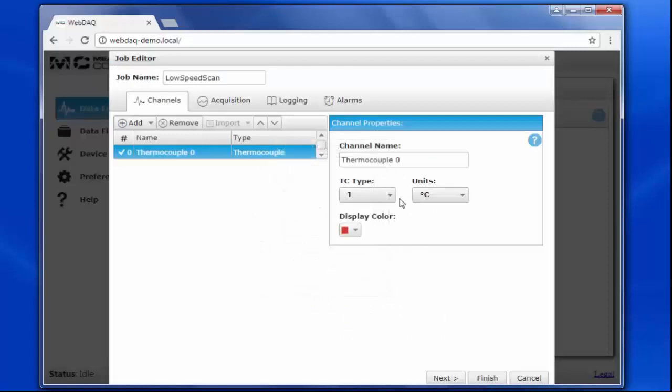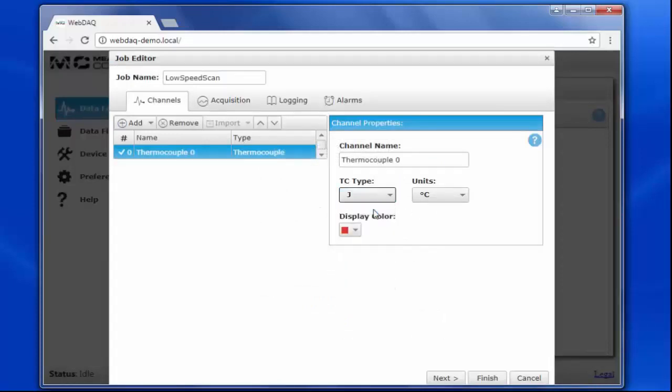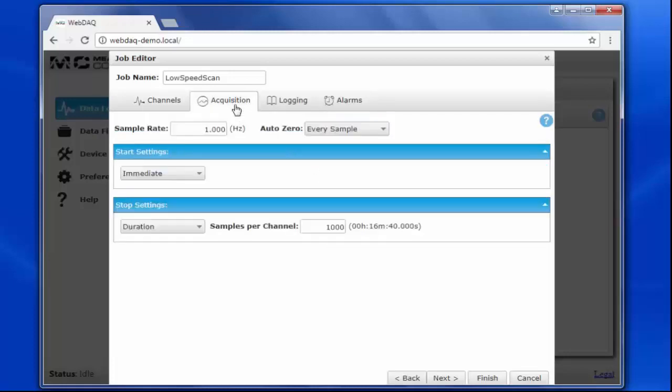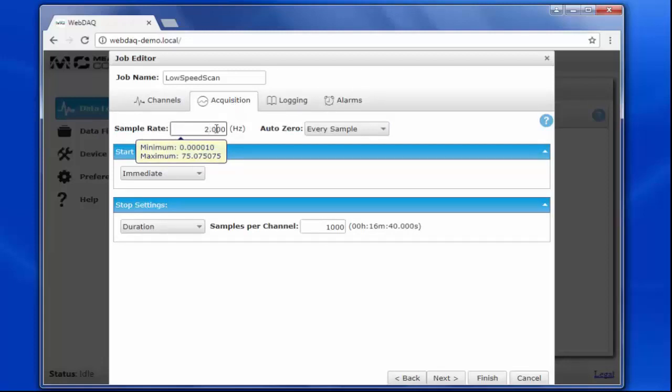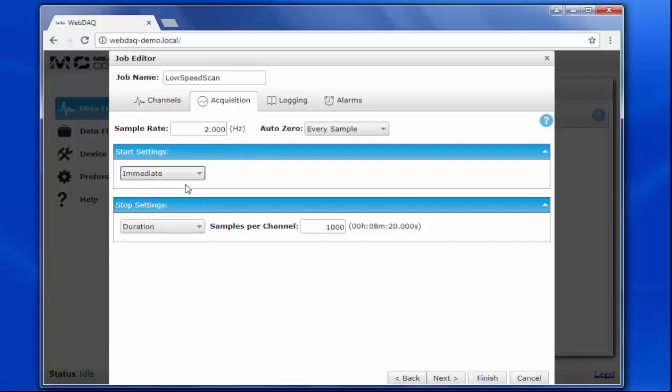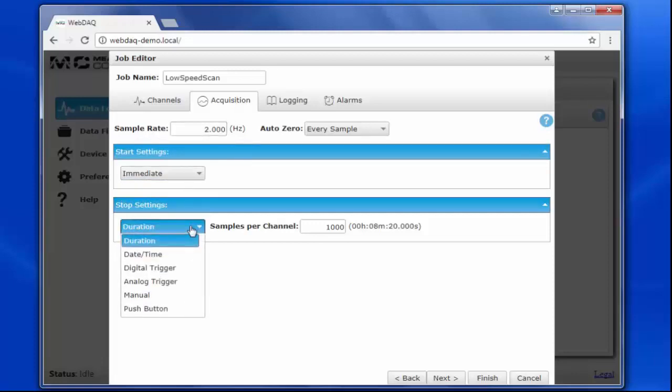Now I can configure the channel properties. My thermocouple connected to channel 0 is type J, and I want the data displayed in degrees Fahrenheit. If I click on the acquisition tab, I can configure the sample rate and any start or stop settings for this job. Let's set the sample rate to 2 Hz, have the acquisition begin immediately, and stop manually when I click on the abort button.